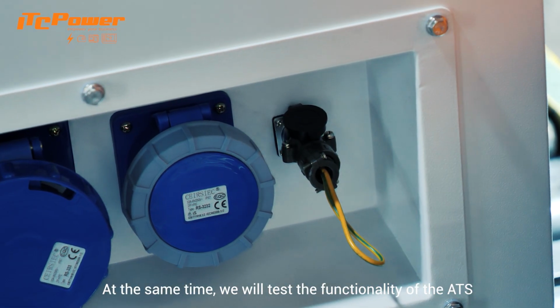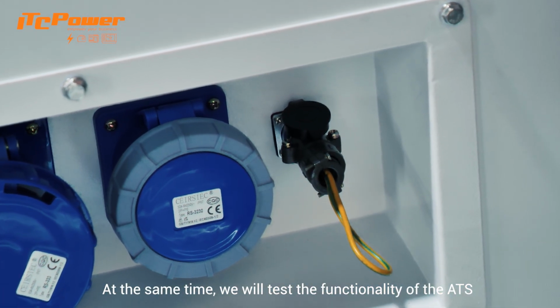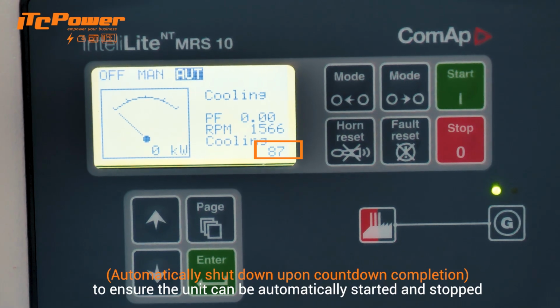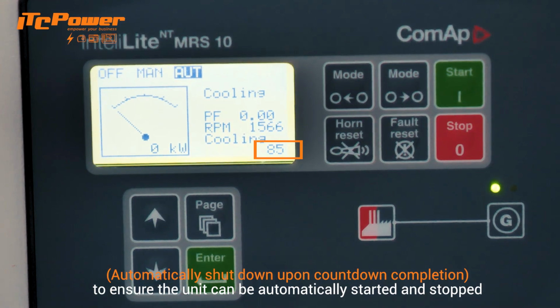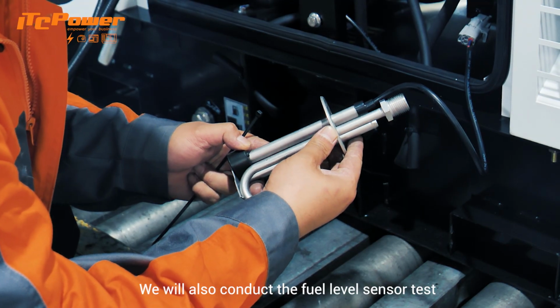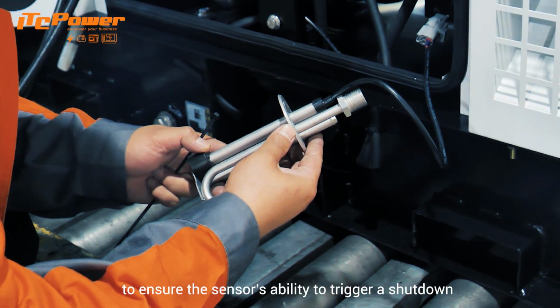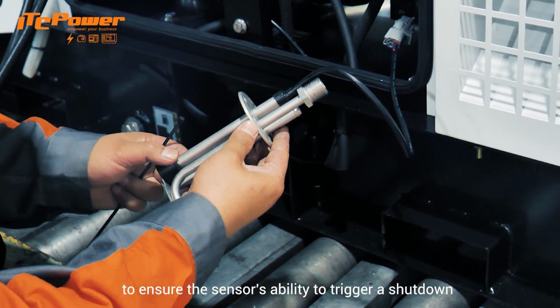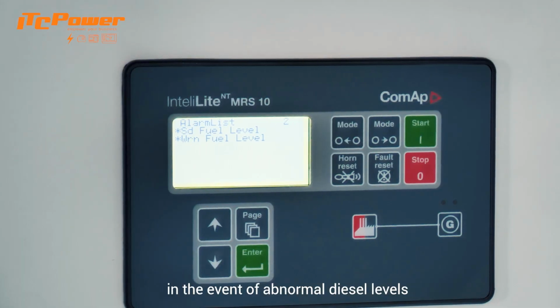At the same time, we will test the functionality of the ATS to ensure the unit can be automatically started and stopped. We will also conduct the fuel level sensor test to ensure the sensor's ability to trigger a shutdown in the event of abnormal diesel levels.